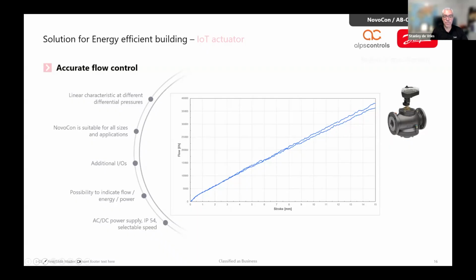Another application which is now rather popular in Europe is what we call 4-pipe changeover. That means one heat exchanger, usually a climate panel ceiling but it could also be a fan coil unit, is doing both the heating and the cooling. Then there's a 6-way valve in between that switches over. That switching over can also be done directly from Novacon, and it has its own algorithm built in.